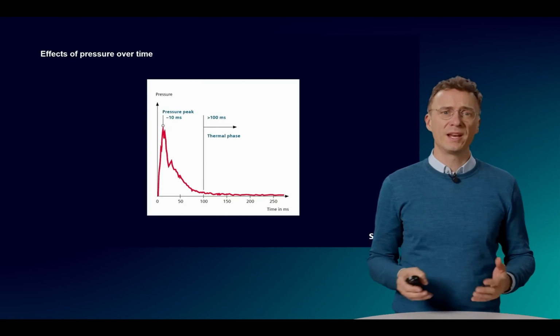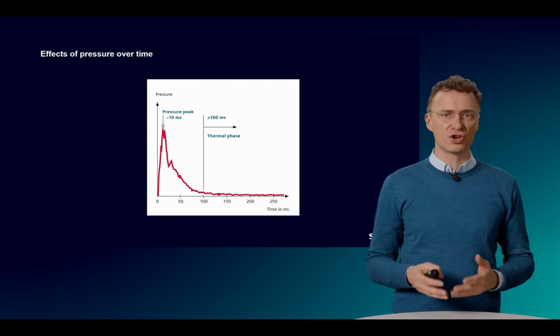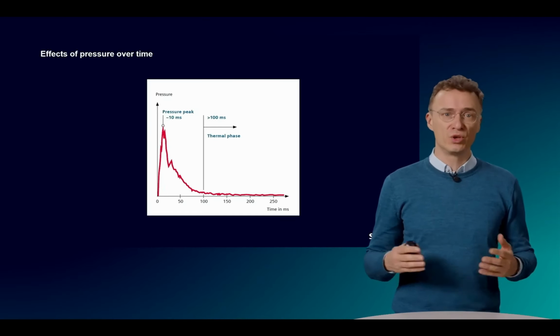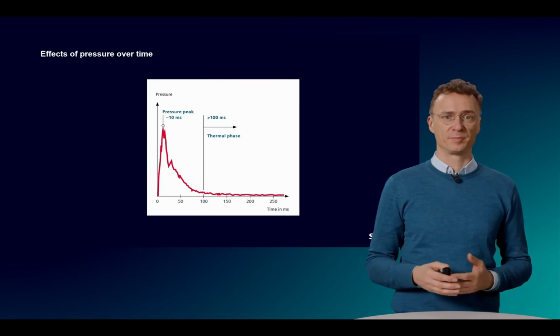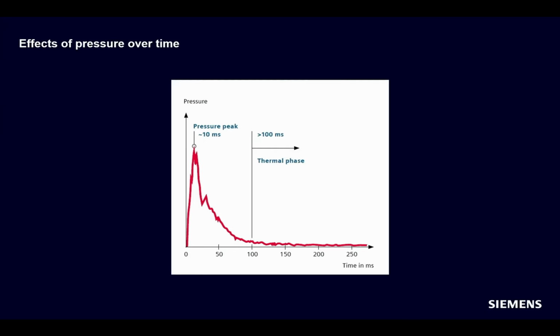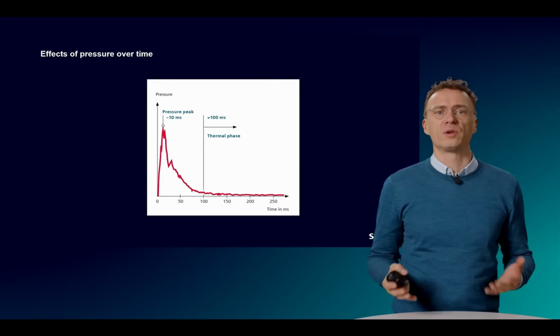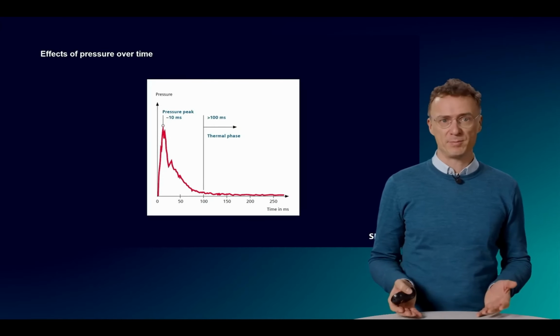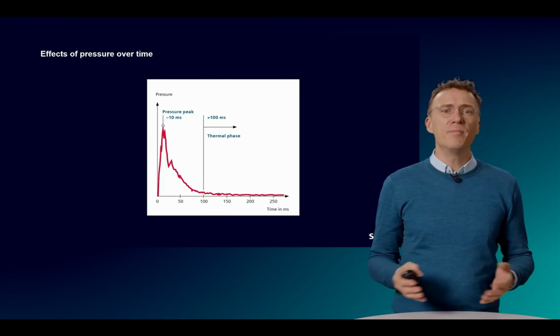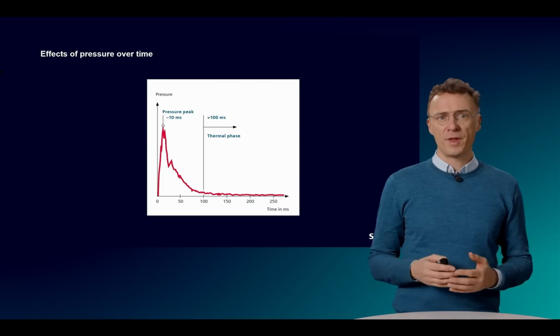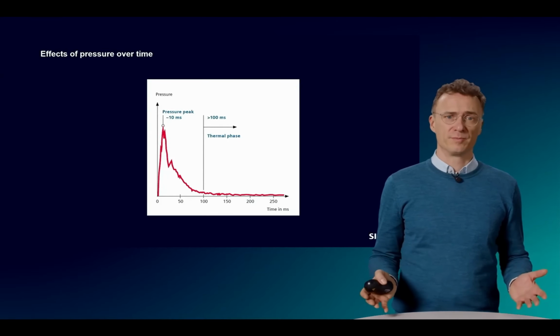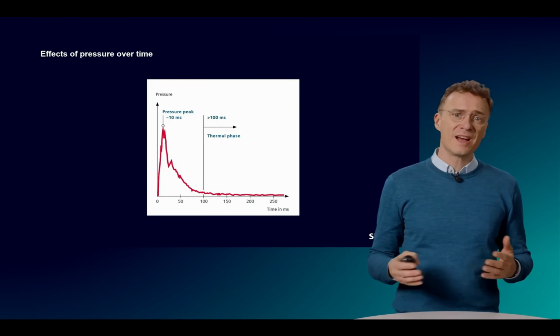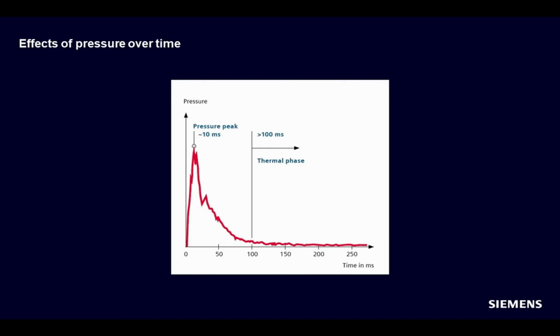This reacts so quickly that you can get ahead of the peak of the pressure curve and can thus also reduce the mechanical load on the system. What does the quenching device do? Well, the device causes an three-pole short circuit on the main bus bar. This short circuit immediately removes the energy from the arc fault and the arc goes out. The resulting short circuit is now switched off by the circuit breaker.